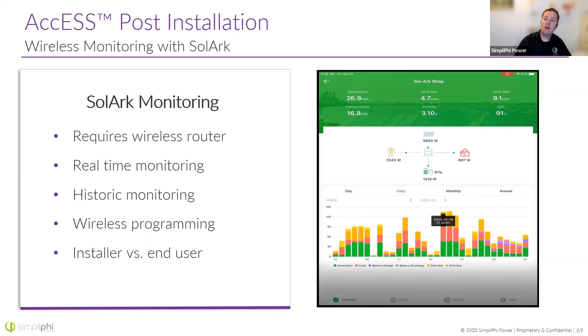There are two levels of the app. One's for the installer, where we can go back and make changes to the set points, which is great. Say you commissioned a system and you're back at the office and realize you didn't do something right, you can go into the app and change some of those set points, adjust that low voltage battery cutoff, maybe play with that a little. The end user doesn't get that ability, so they can't mess with their system, but they still get what they want to see, which is what's my battery capacity at, what am I using, am I backfeeding the grid. Sol-Ark has got a great product with that.